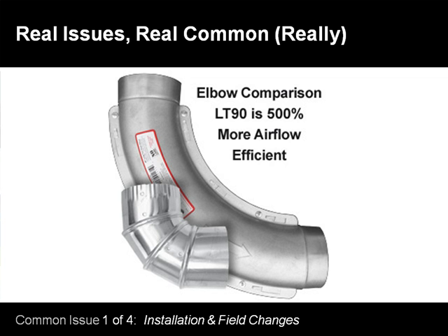So the engineer put in 10%, and the contractor put on 20%, and now, hey, let's make it twice as big as it has to be. That's how we're now in the position we are today. So now the pendulum swung the other way, and we're saying, just give me enough fan to push the amount of air out that I'm talking about, put a little dirty, just to overcome when the coil or the filters get a little dirty, and that's it. And that's all we're going to do. Same thing with pumps and valves. So you put a bunch of fittings in there that wasn't in that design intent, and you may have a pump that looks undersized, when in actuality it's sized correctly if the design was installed.